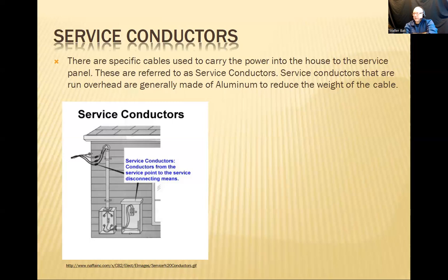However, if you carry wires overhead—from the service demarcation point, hanging overhead, going to the hydro pole where the transformer lives—it's overhead, hanging, and it weighs. So although aluminum isn't the better choice for conductivity and current carrying features, it's lighter. That's why aluminum is used for hanging or overhead conductors.